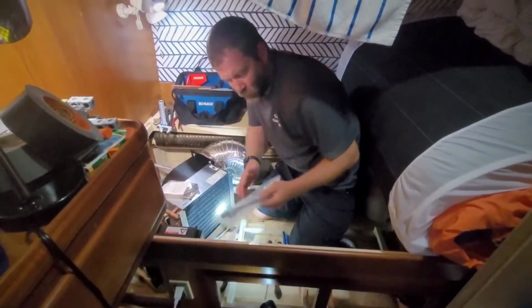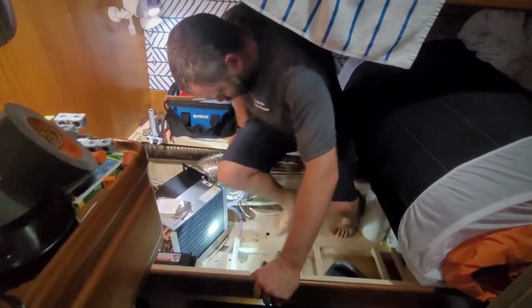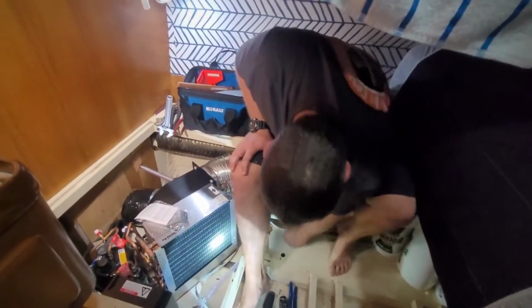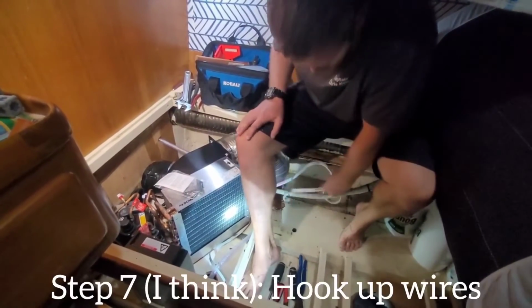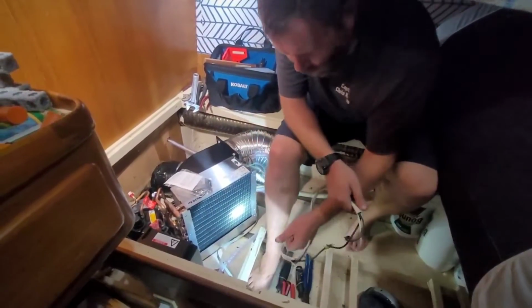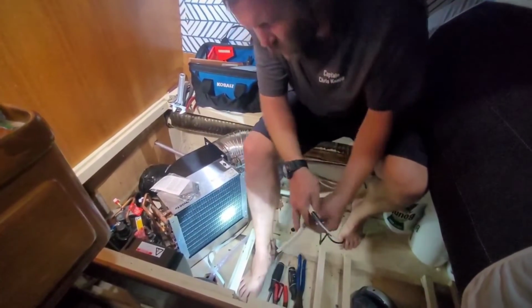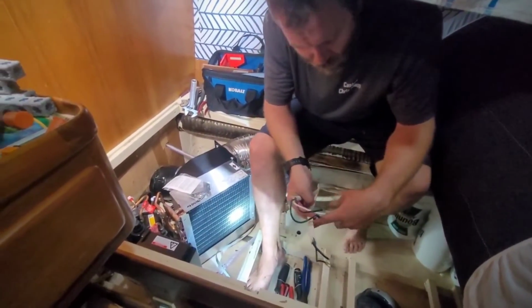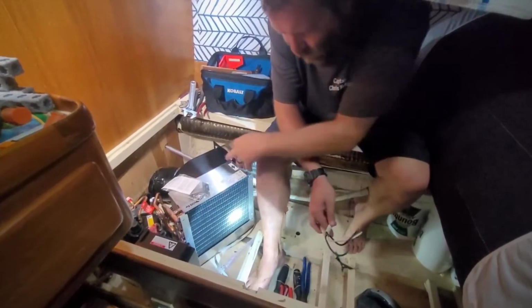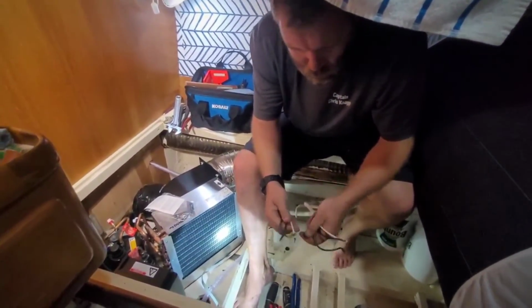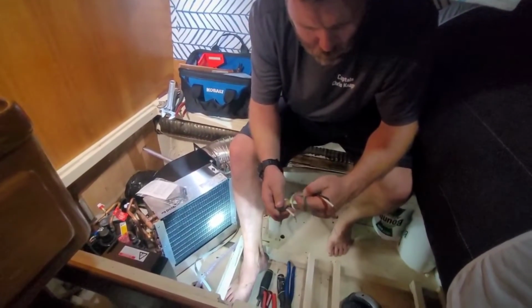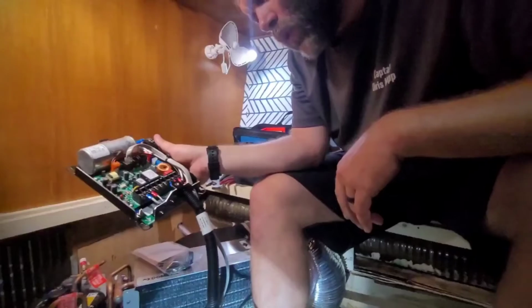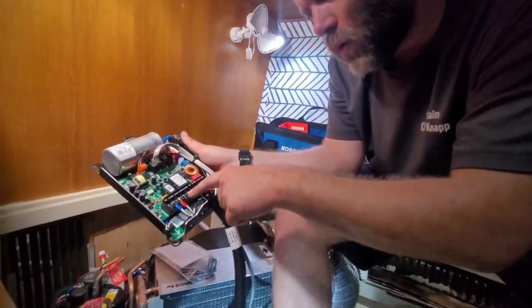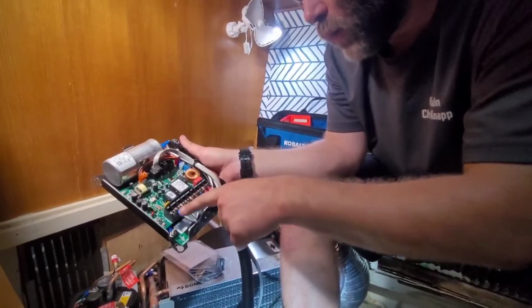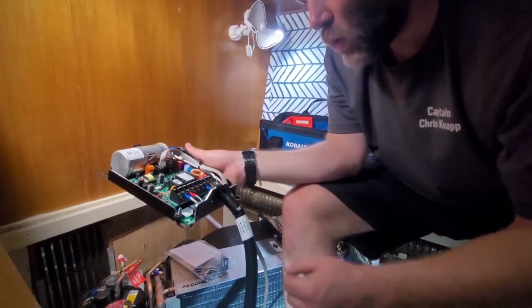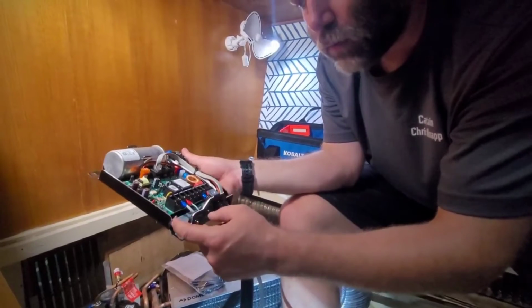Electrical - got two wires we gotta hook up right here. One goes to the pump relay box, which turns on the pump when the air conditioner turns on; if the pump's not already running, it activates it. The other is just power to the actual unit itself - usually a hot, a neutral, and a ground. So pump goes here, then line 1, line 2, and ground goes right there.